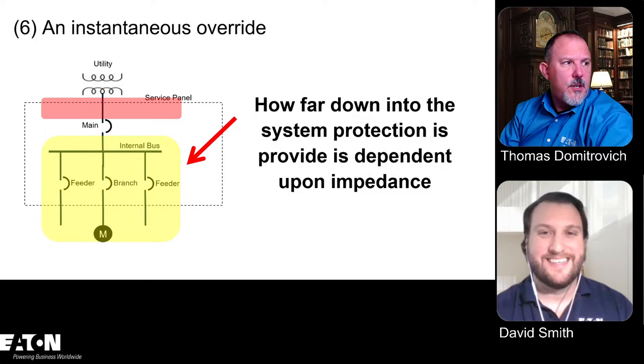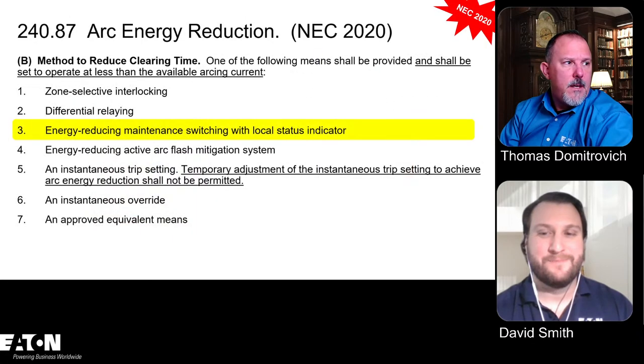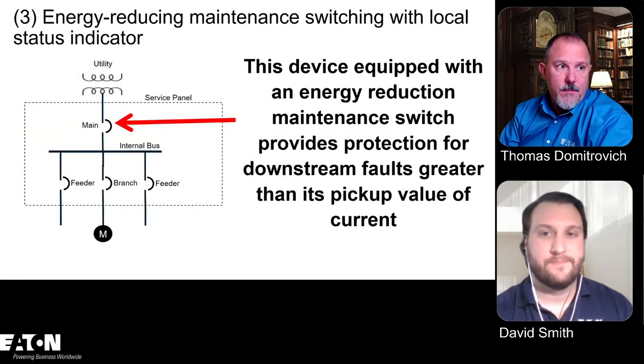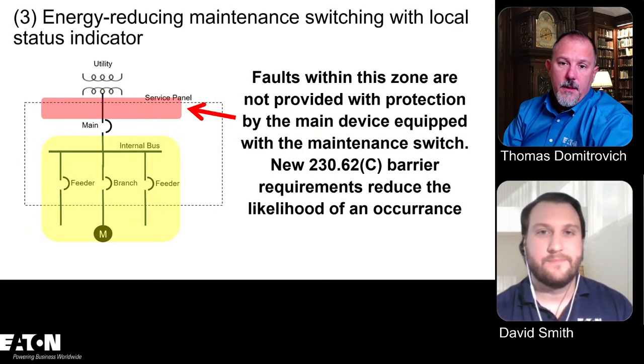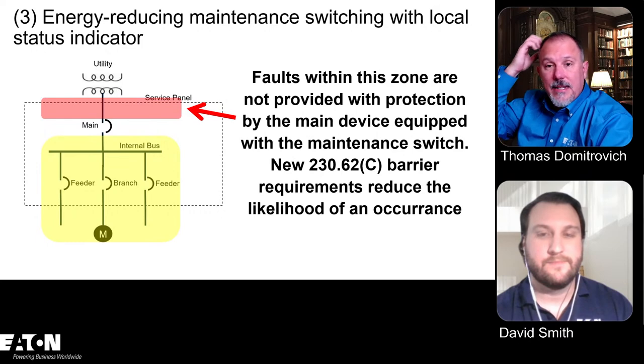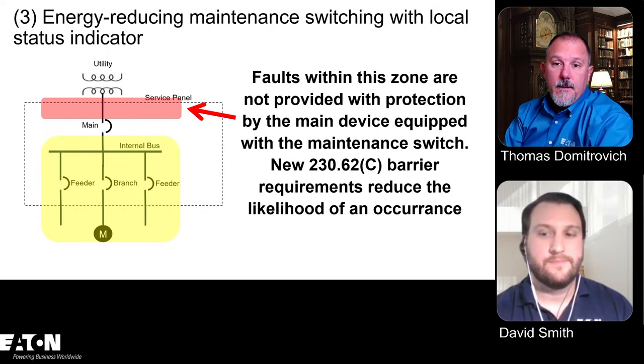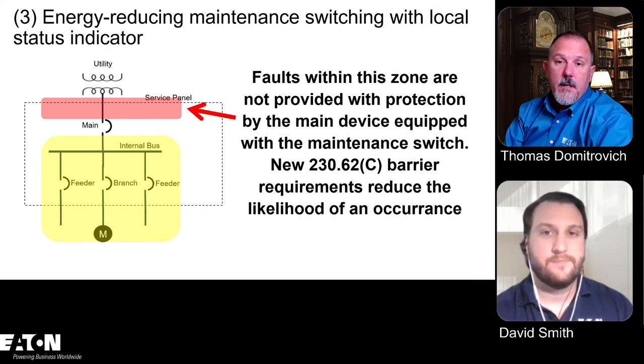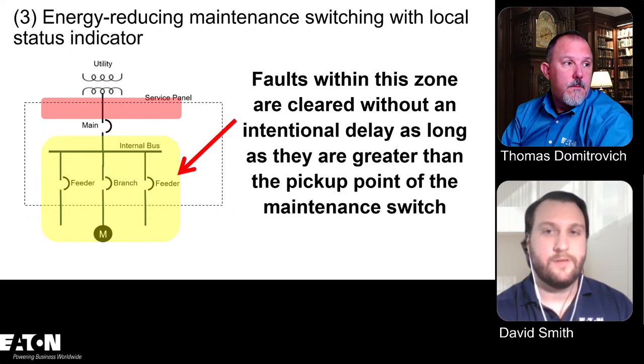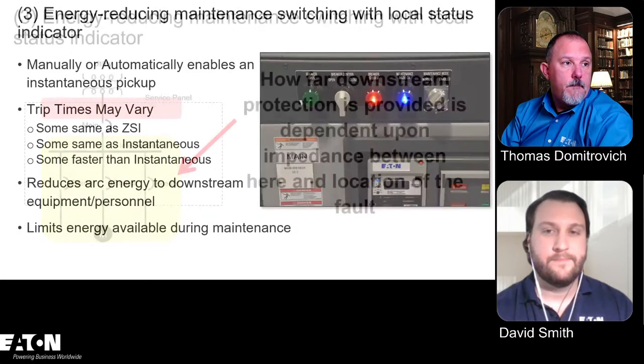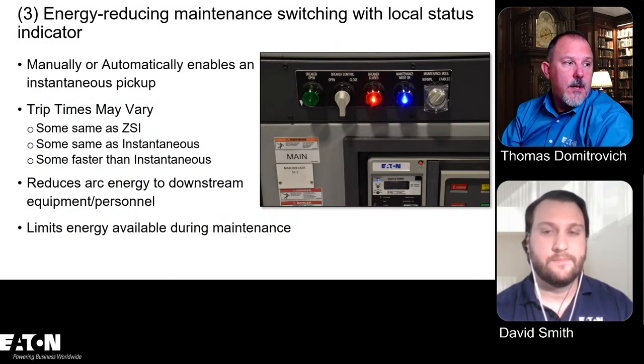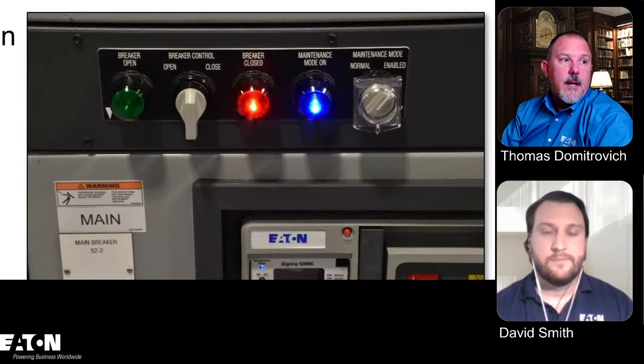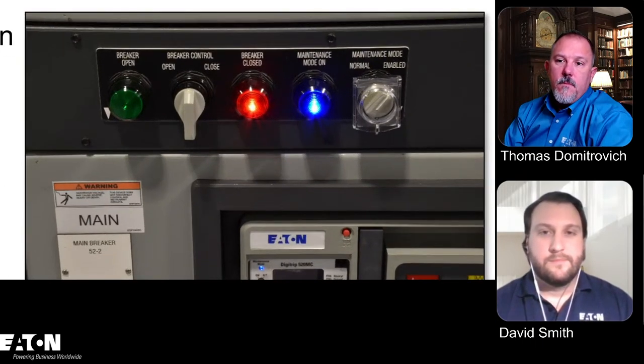And that's your instantaneous override. And there's your arc reduction maintenance switch, whose protection scheme looks exactly like the instantaneous. Very similar, it's just a lower value. And that's what it'll typically look like on a power circuit breaker lineup.